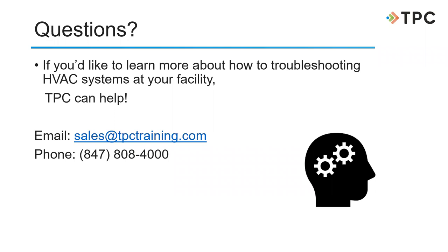Speaking of the condenser, I think we're getting some good questions on the condenser side of things. What is the best way to clean a condenser? Water. Making sure you do a proper lockout/tagout, and water is the best cleaner. Water will clean a lot of your dirt off. And again, making sure you're locked out, making it electrically safe, because I've seen guys in class where they show me their fingers and they have three fingers missing because the condenser fan motor kicked on and tipped their fingers off. Be very careful when you're doing it.